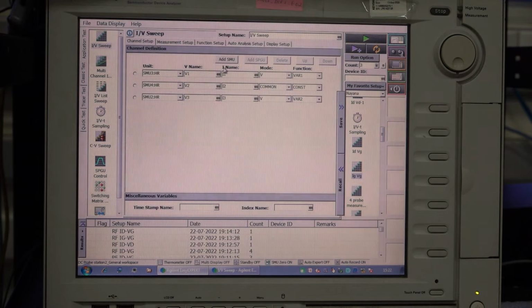So for 4 probe measurements, basically we can add one more SMU. So this SMU will basically vary the step voltage, and one more terminal will be grounded, because normally we use the 4 terminal method to avoid the contact resistance and the probe tip resistance. If we use the same measurement setup with the contact resistance and the probe tip resistance, we will get an error value. We cannot measure low resistance accurately. So in order to avoid contact resistance and cable resistance, we go for the 4 probe measurement technique.